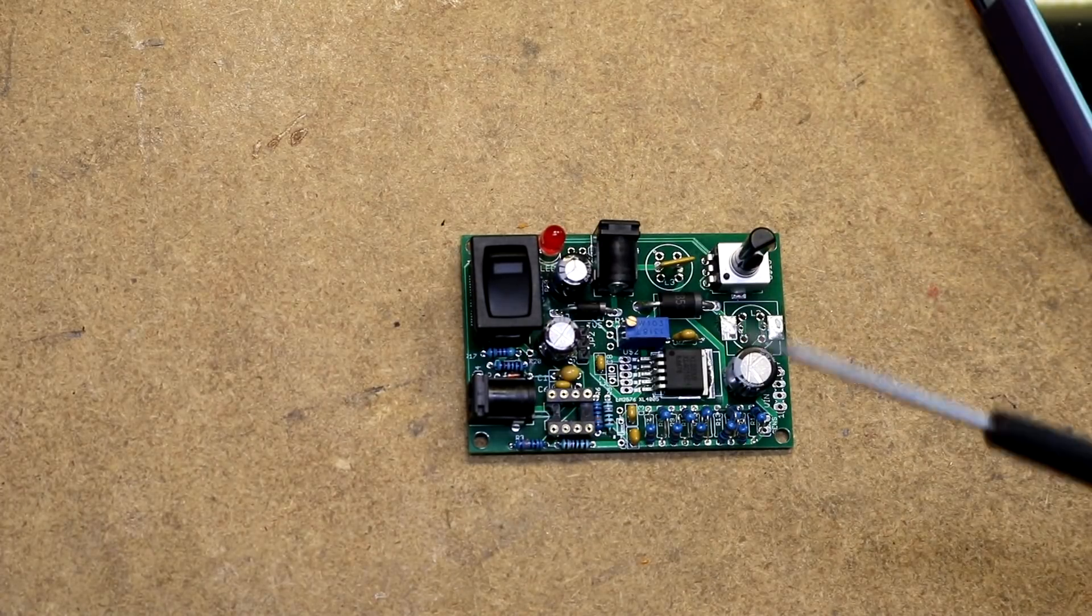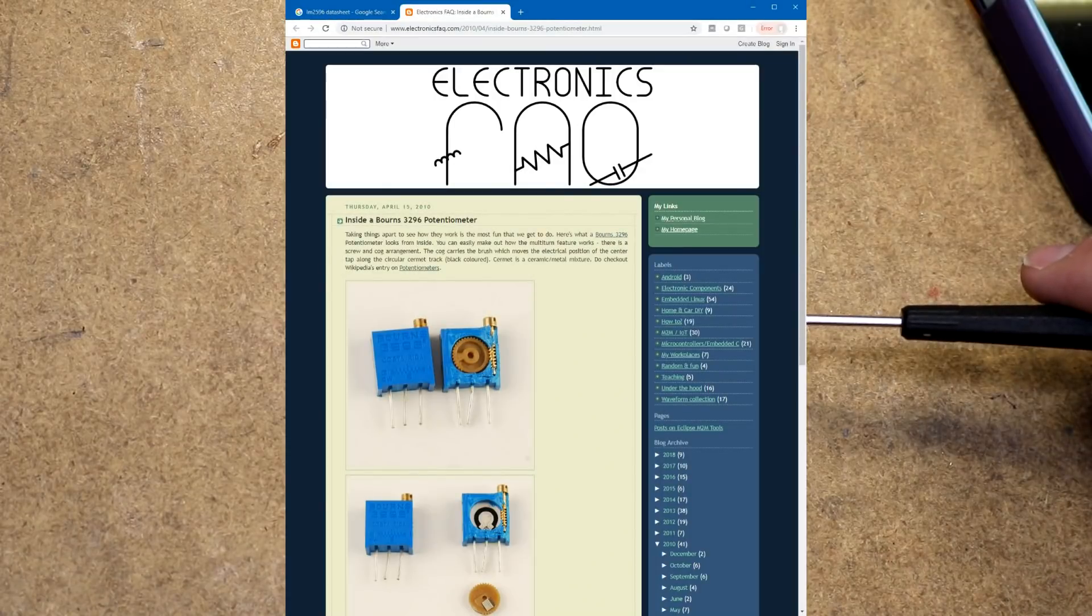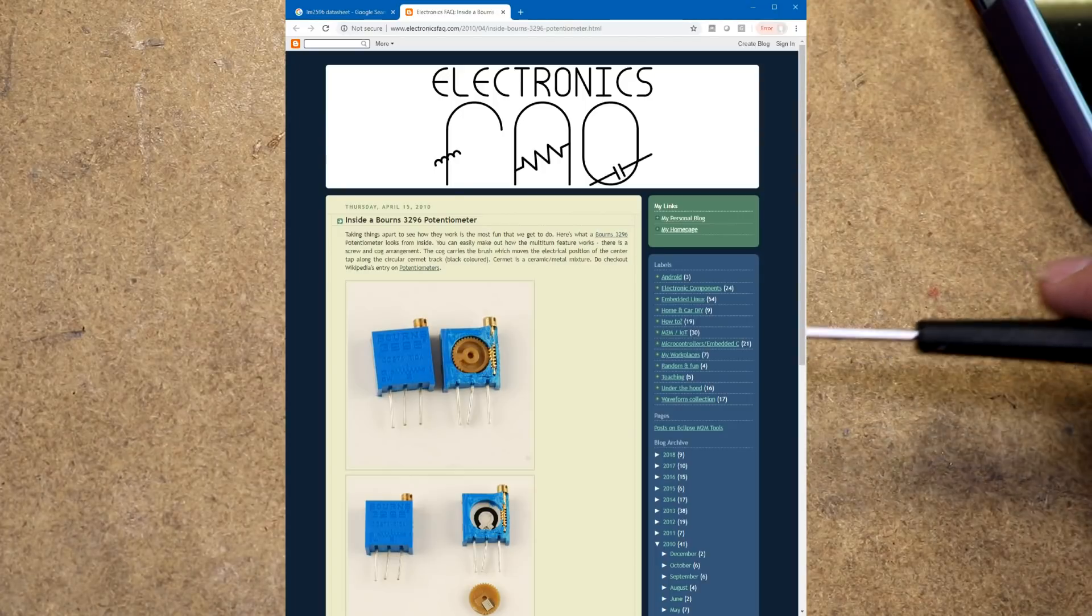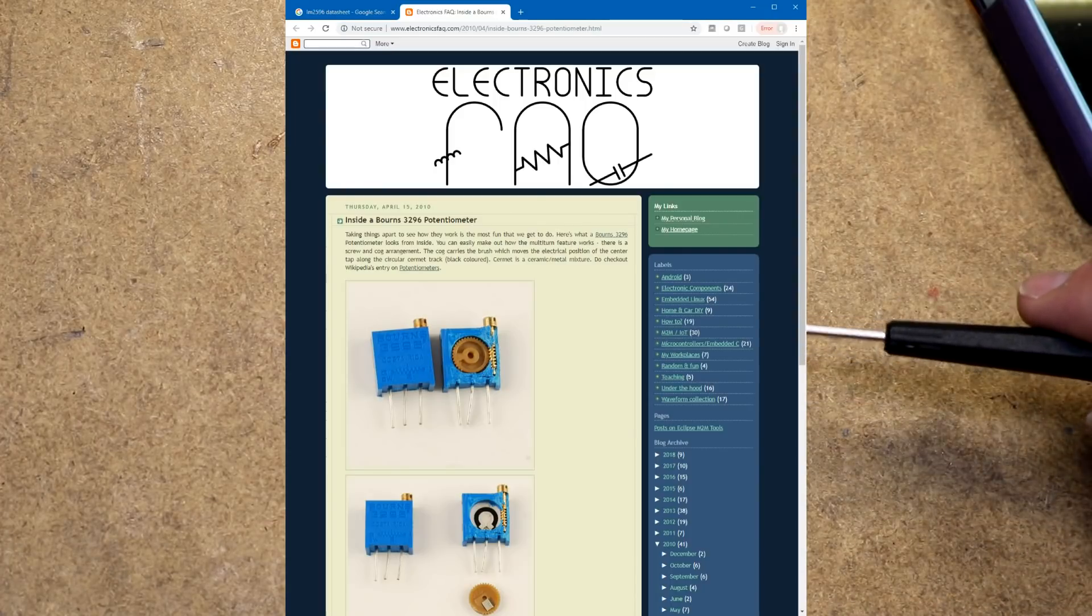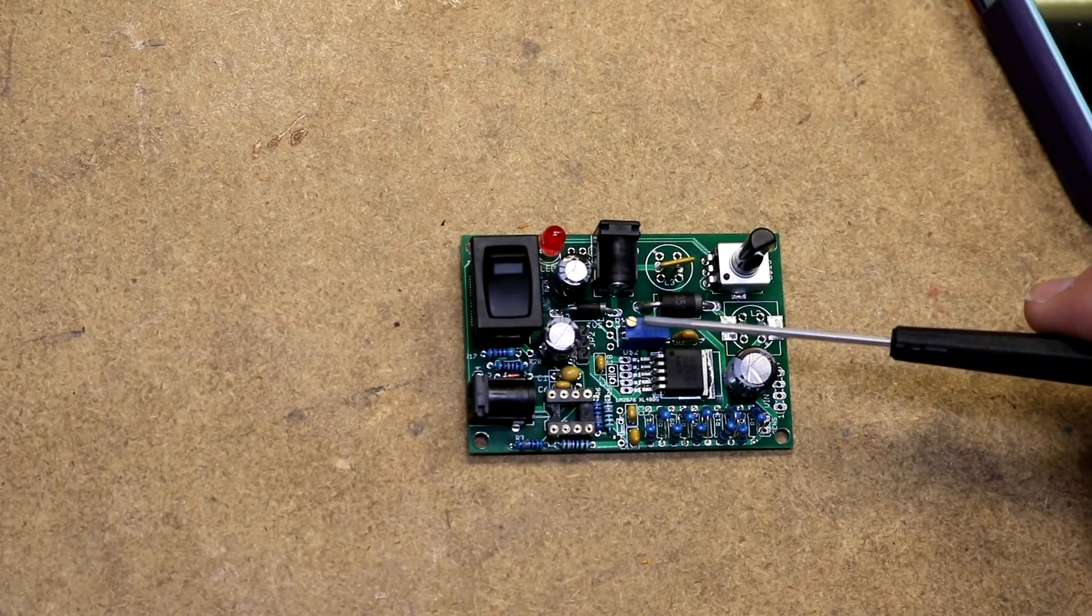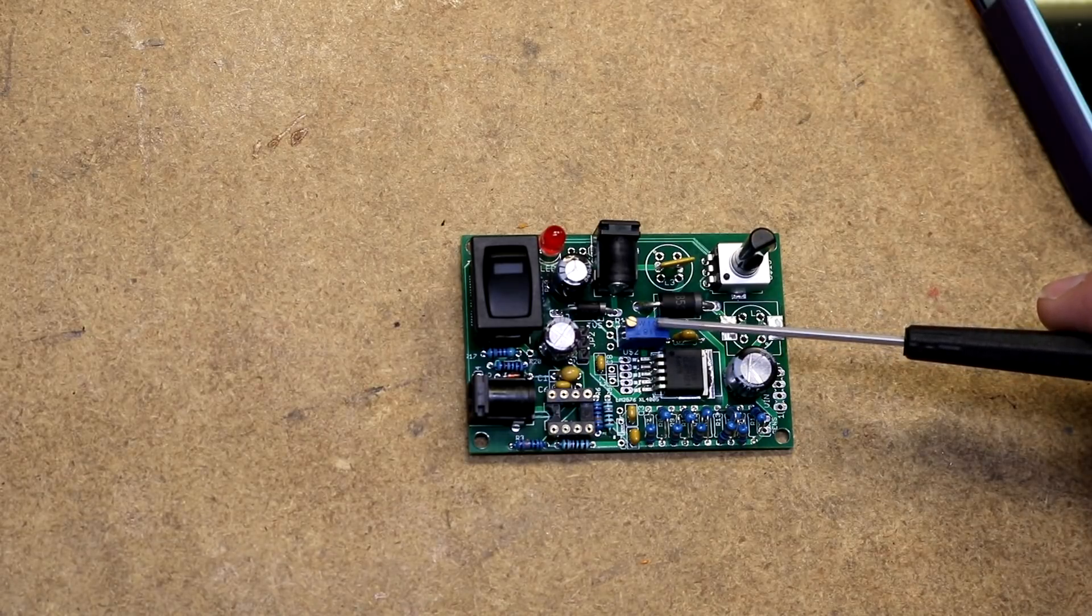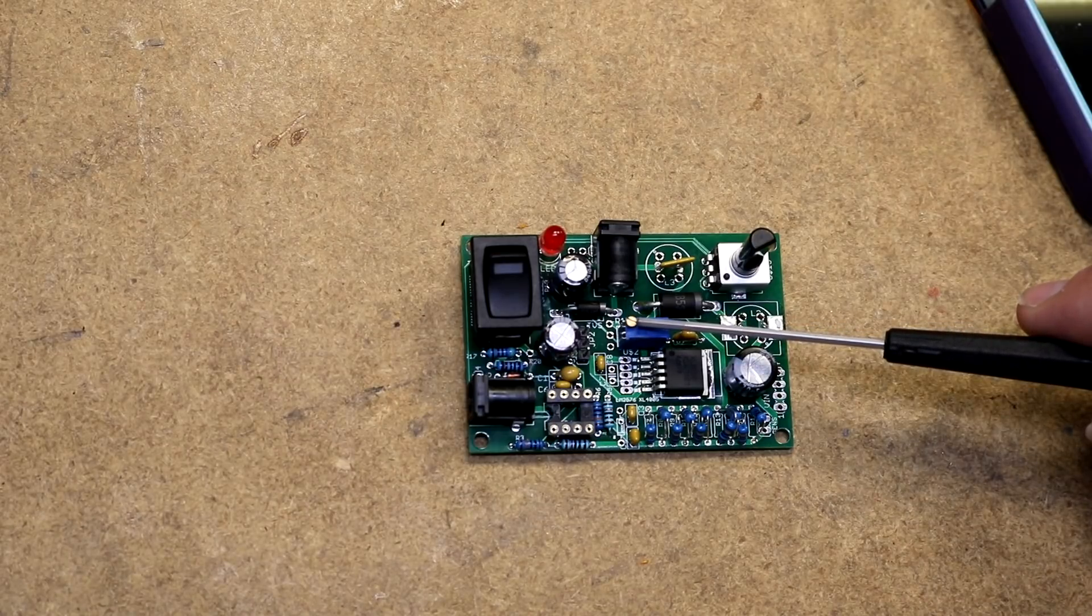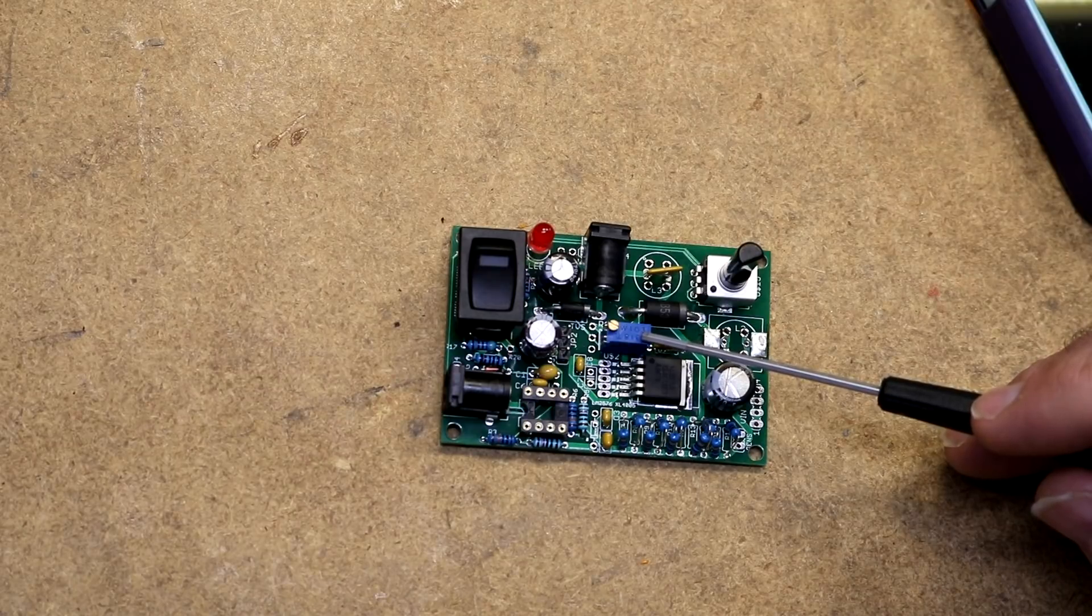The problem, these devices, they're inherently an electromechanical device. If you cut one open, I think you'd find that there's a worm gear attached to this screw that turns kind of a rotating potentiometer. Anytime you have like a worm gear system like that, you run into backlash and slop in the gear. So if you turn this clockwise and pass your set point, and then turn counterclockwise to get back to where you want it set, there'll be a little bit of slop in there. And I found these seem to have a lot of slop. For example, if I passed my set point, I would have to turn this back two turns before the reading even started moving again.